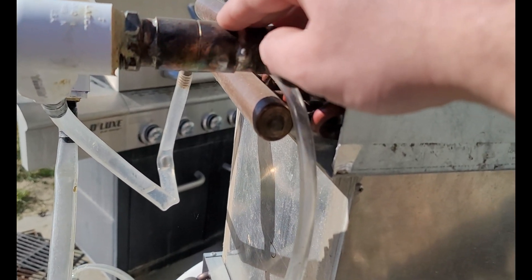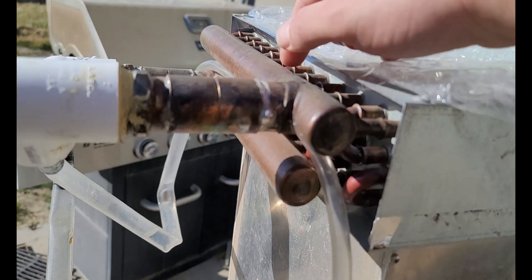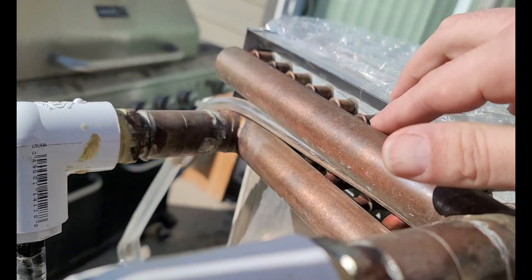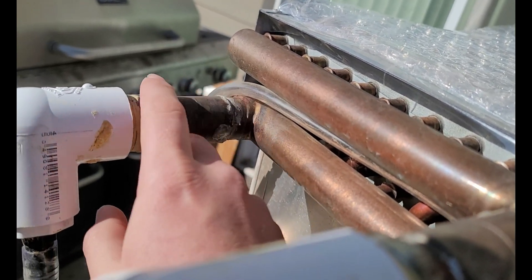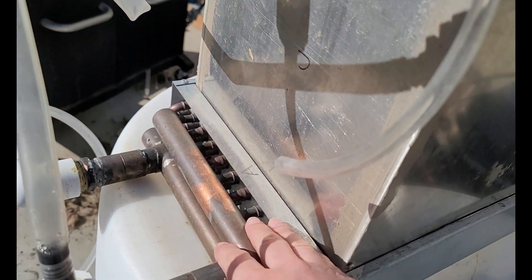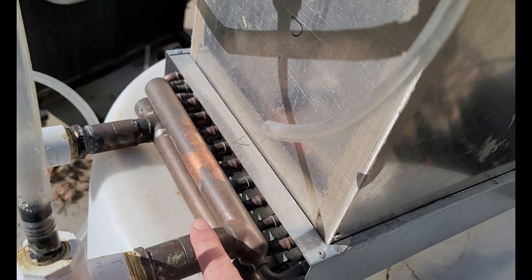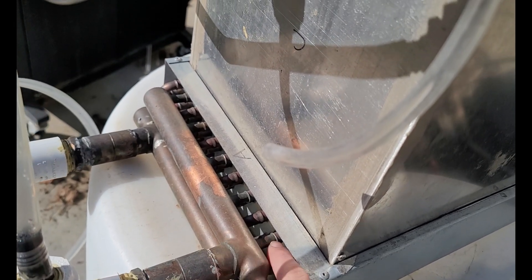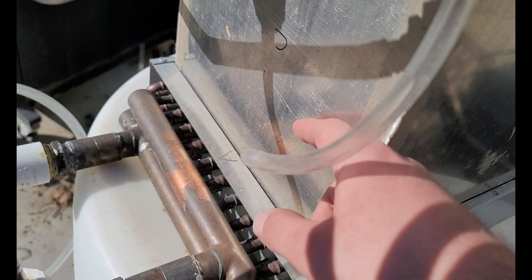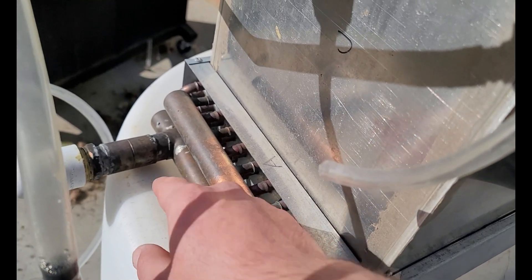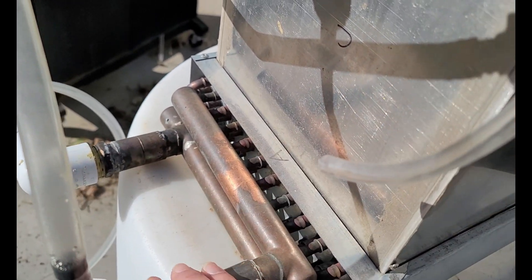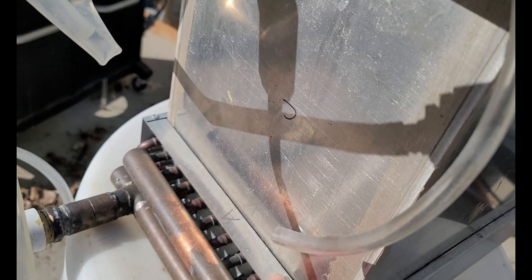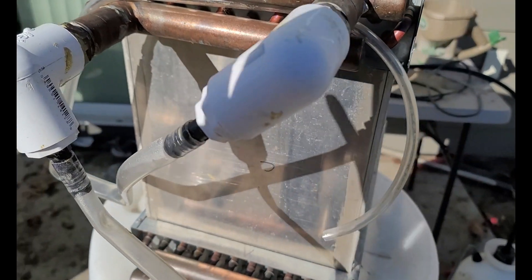The hot water comes in through here and goes through all these little channels, comes out the bottom a little bit colder, and then it goes down to the second radiator on the bottom. It cools it down a second time and then it comes out this way and goes out to the cooler. The idea is basically to cool down the water before it goes back into the server room.